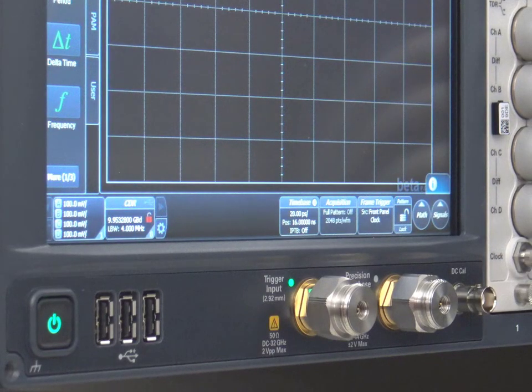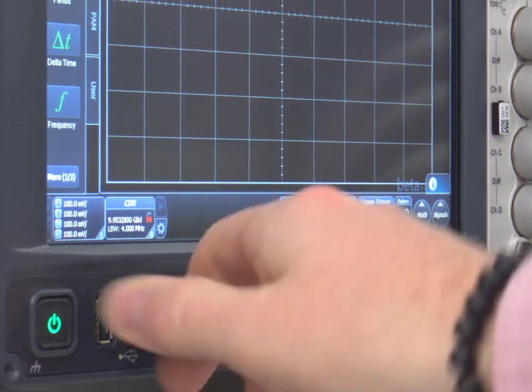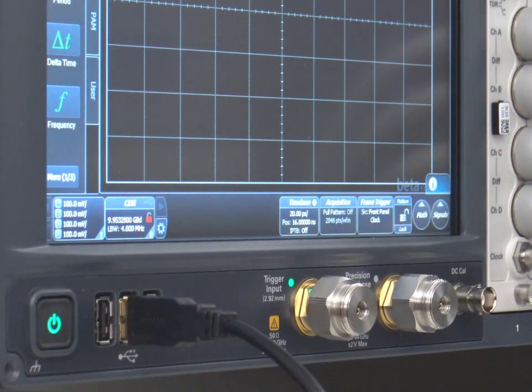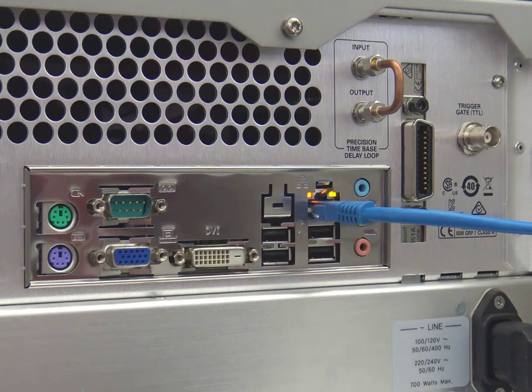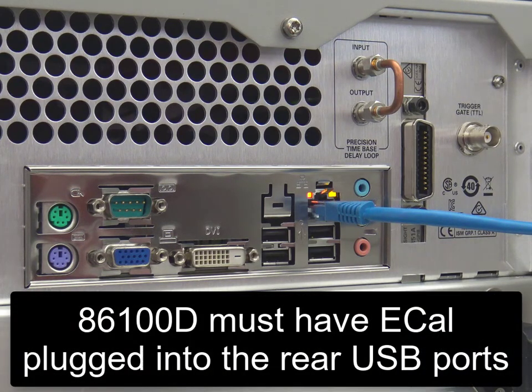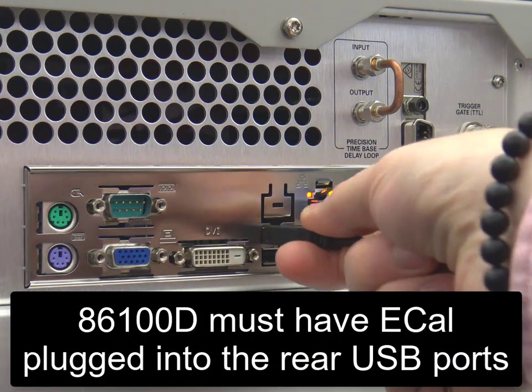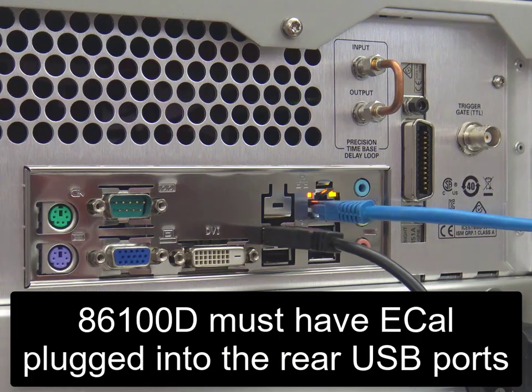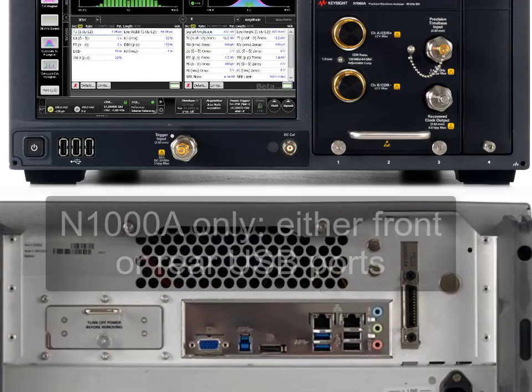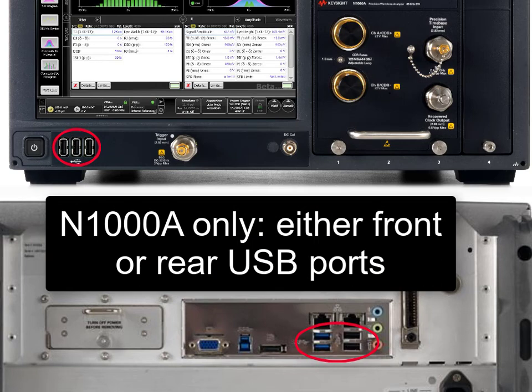To start this calibration, first plug in your eCal module into a USB port on the mainframe. If you are using the 86100D, then you must plug the eCal module into the rear USB ports. With an N1000A mainframe, you can use any USB port.